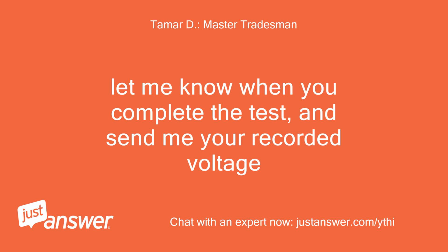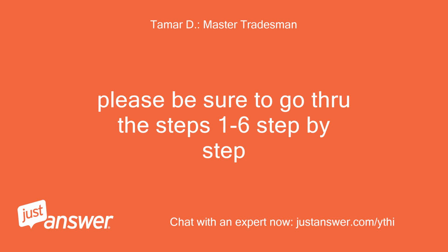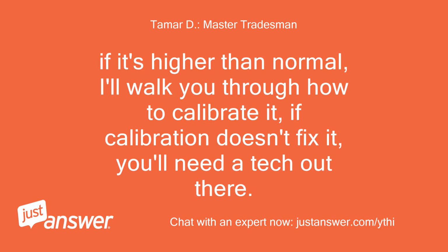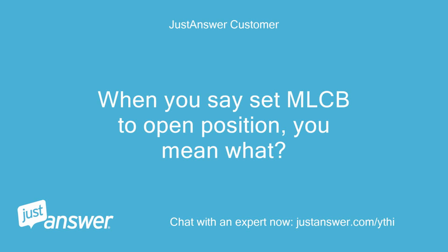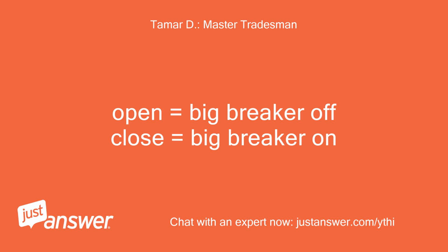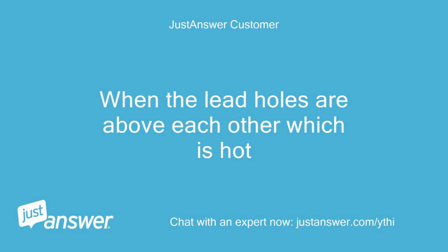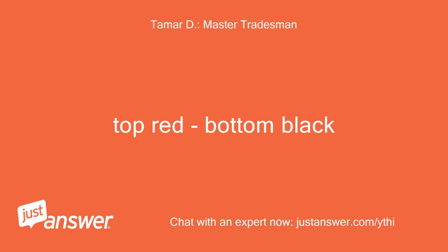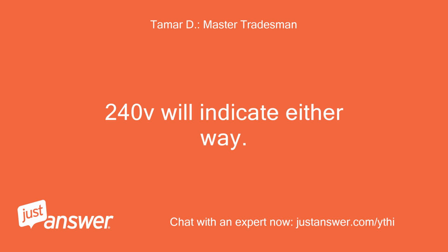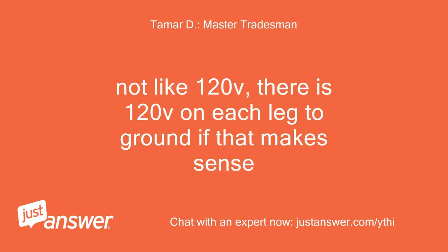Let me know when you complete the test, and send me your recorded voltage. Please be sure to go through steps 1 to 6 step by step. If it's higher than normal, I'll walk you through how to calibrate it. If calibration doesn't fix it, you'll need a tech out there. When you say set MLCB to open position, you mean what? Open equals big breaker off, close equals big breaker on. When the lead holes are above each other, which is hot? Top red, bottom black. 240V will indicate either way. Not like 120V, there is 120V on each leg to ground, if that makes sense.